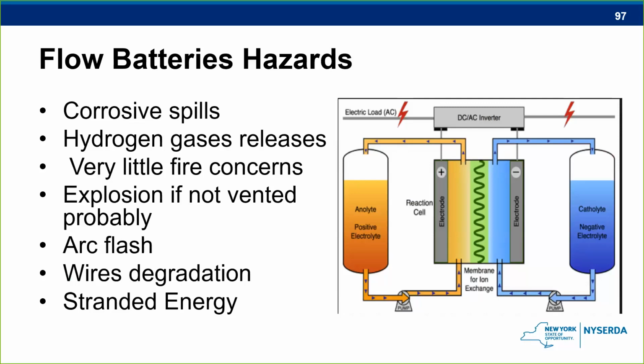Arc flashing is another thing, shutting these things down, large amount of energy. We've got to be concerned about that. Wire degradation, and we'll see that sometimes with rodents. When these things are outdoors, rodents get in there and they actually start to chew away at the wires, or they'll actually degrade. Maybe some of this electrolyte may actually spill or drip onto some of the wiring, and that's a concern for us too.